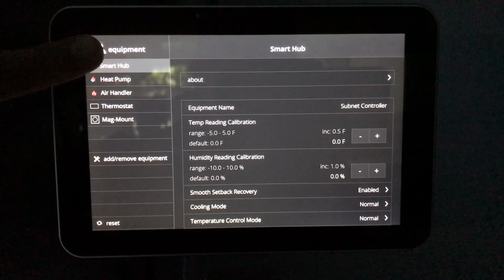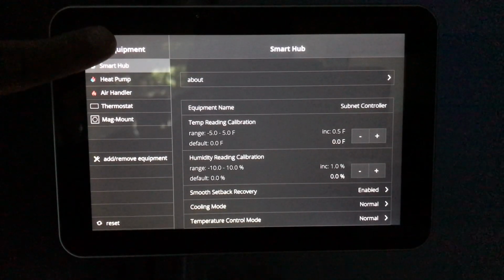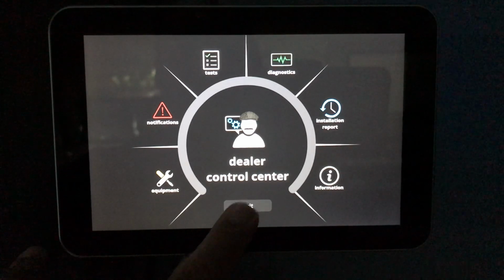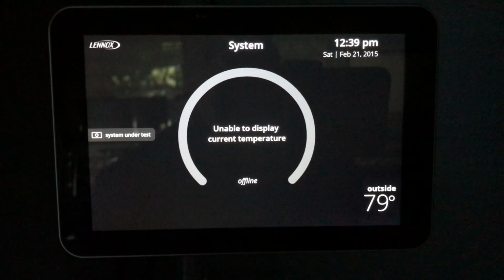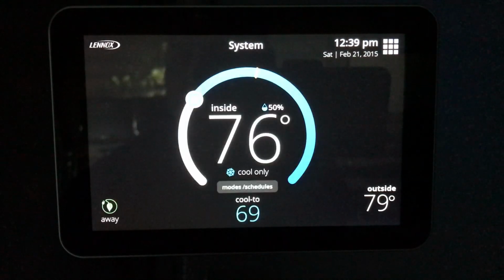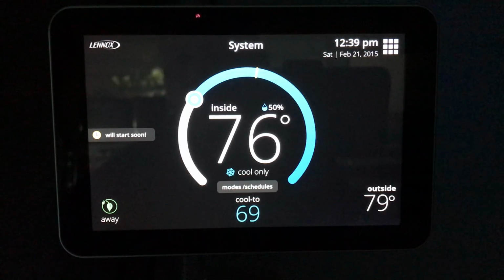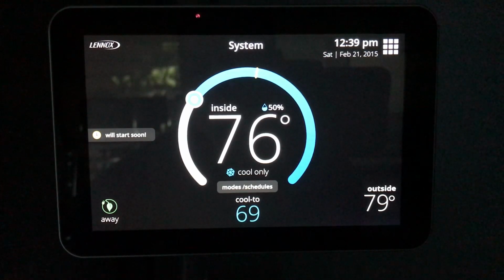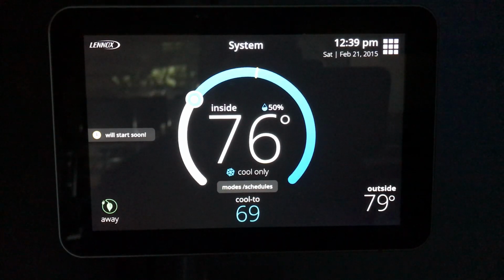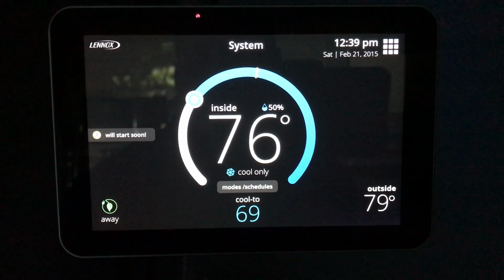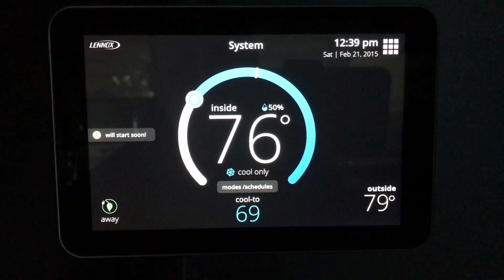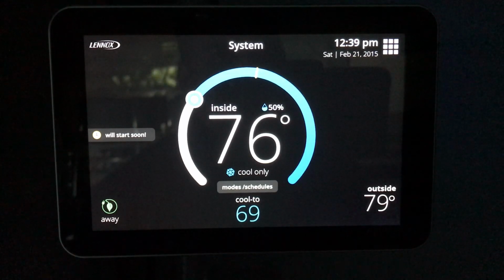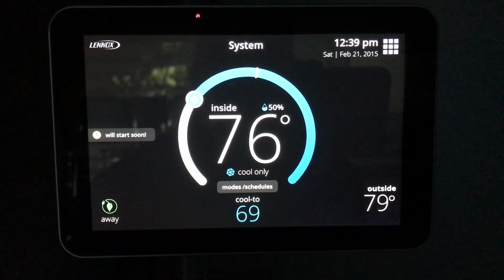Now once you've got your settings dialed in, we're just going to push equipment at the top left to exit out of the menu. And the thermostat will go offline for just a few seconds. And when it comes back up, I've noticed some thermostats will adjust nearly instantly, while others take up to 15 minutes to adjust. So that's why I say it's important to have the psychrometer, as long as you know you're doing the plus and minus dialed in, you may not see the temperature setting change instantly, but give it another few minutes and it will adjust. So right now it's showing 76 degrees here in our technician room. It's not 76 degrees, it's probably at best 71, because remember I had it set at +5. So it will take just a few minutes, but it will adjust back and start to show 71.